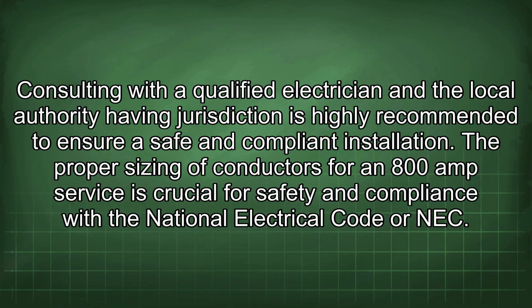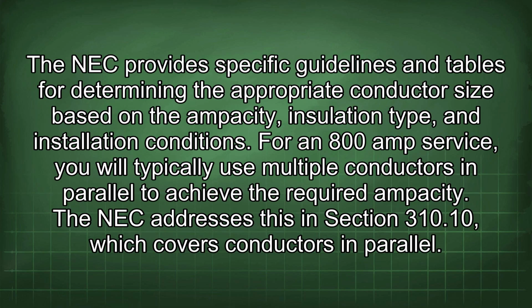The proper sizing of conductors for an 800 amp service is crucial for safety and compliance with the National Electrical Code, or NEC. The NEC provides specific guidelines and tables for determining the appropriate conductor size based on the ampacity, insulation type, and installation conditions. For an 800 amp service, you will typically use multiple conductors in parallel to achieve the required ampacity. The NEC addresses this in section 310.10, which covers conductors in parallel.